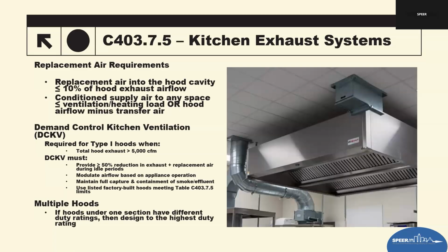And then the demand controlled kitchen ventilation requirement for Type 1 hoods. One of the biggest items here is the mandatory use of those controls when the total Type 1 hood exhaust exceeds 5,000 CFM. That DCKV system must be able to reduce exhaust and makeup air by at least 50% during idle periods, so modulate airflow based on actual cooking activity. A lot of that will probably be in the manufacturer's data. Always maintain full smoke capture and containment.